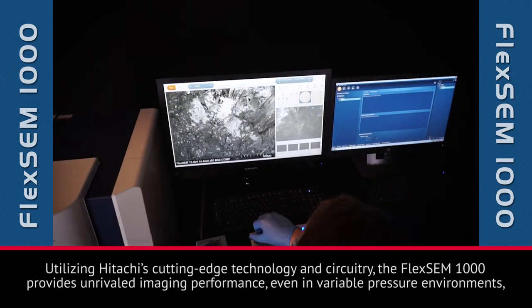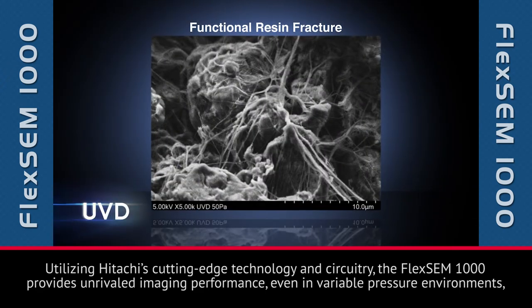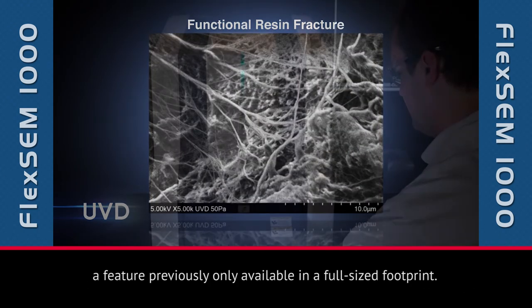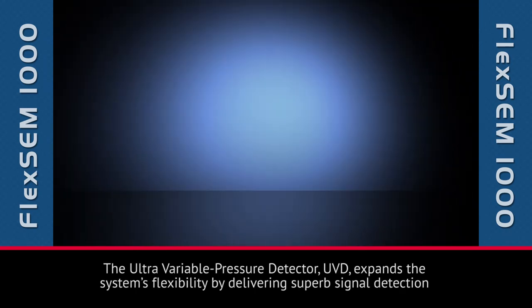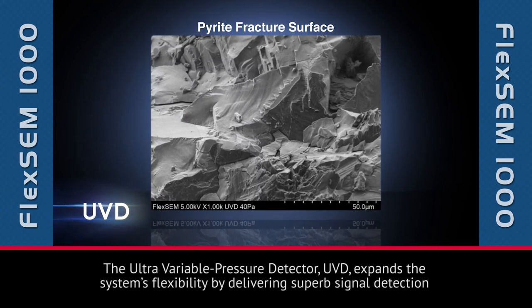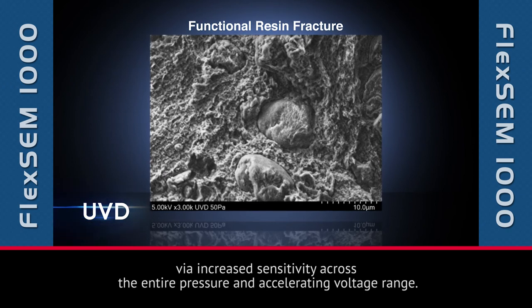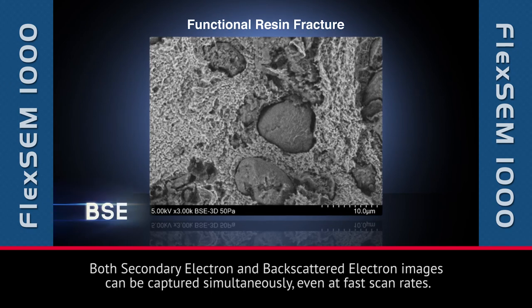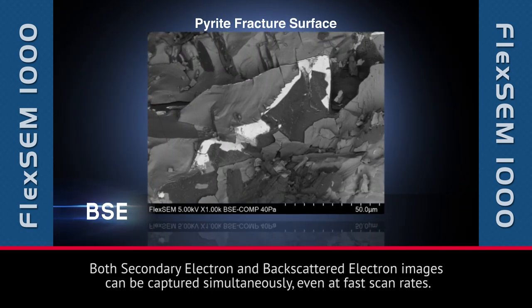Utilizing Hitachi's cutting-edge technology and circuitry, the FlexSEM 1000 provides unrivaled imaging performance, even in variable pressure environments, a feature previously only available in a full-size footprint. The ultra-variable pressure detector, UVD, expands the system's flexibility by delivering superb signal detection via increased sensitivity across the entire pressure and accelerating voltage range. Both secondary electron and backscattered electron images can be captured simultaneously, even at fast scan rates.